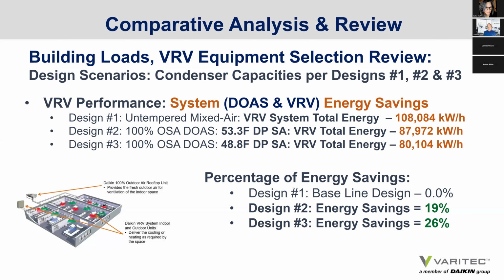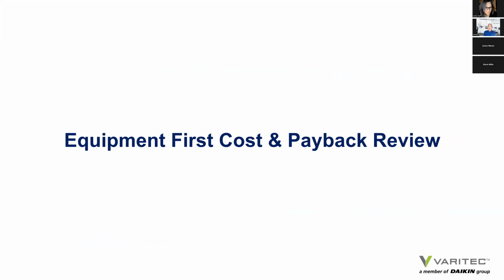How does this actually pencil out with regard to performance? Design number two consumes 19% less energy than the untempered design scenario, and the low dew point DOAS design strategy saves 26% more efficiency in Phoenix, Arizona, or in a Sonoran Desert above an untempered design solution. Well, here's the big challenge that we always have.